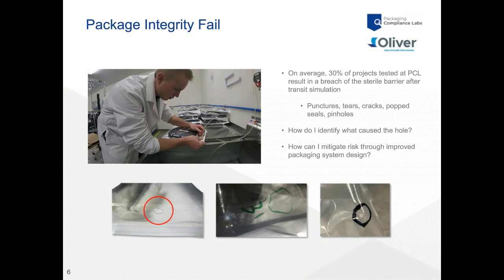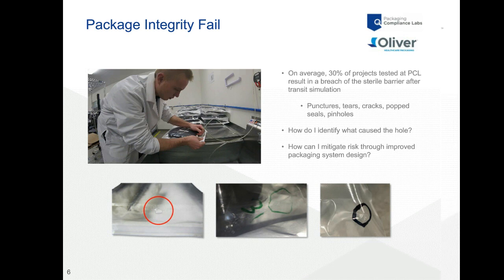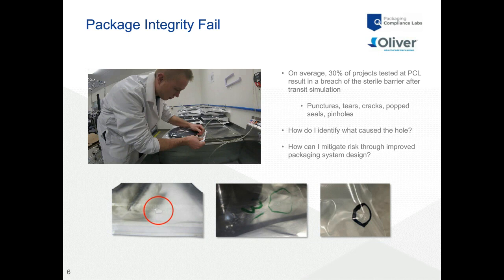After transit testing, we investigate the packaging inside the boxes to determine if there's been a breach of the sterile barrier. We do this with bubble leak integrity testing, among other methods. This involves submerging the package underwater, inflating it with air, and checking for escaping air, which would indicate a hole in the pouch or bag, a cracked tray, or a puncture.